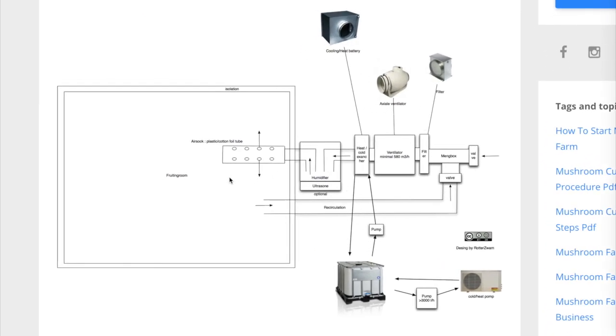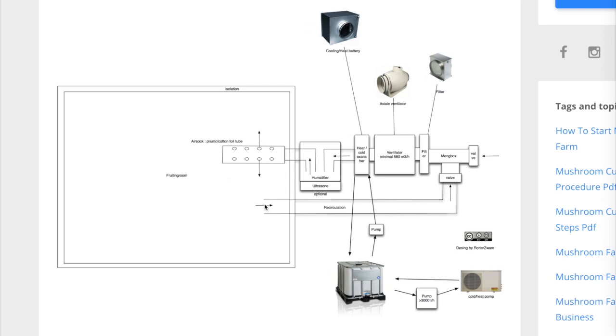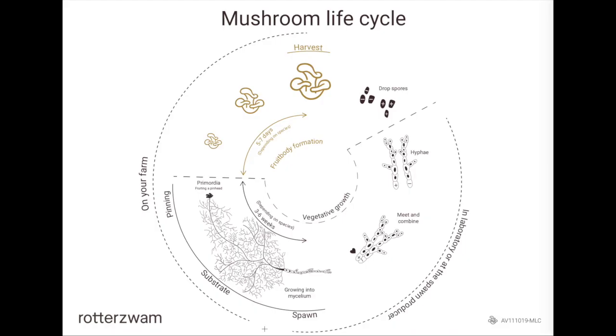That again depends on the different phases — the growing phase or the incubation phase — which is a little different in terminology due to language, since we are both not native English speakers. So you have two phases: the incubation or growing phase and the fruiting phase, where the fruit bodies are forming. You need to accommodate both phases through your ventilation system.